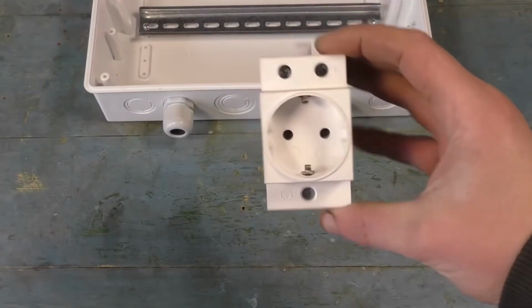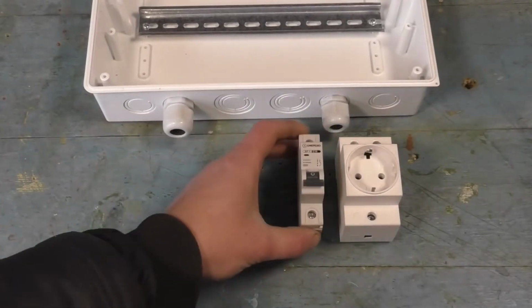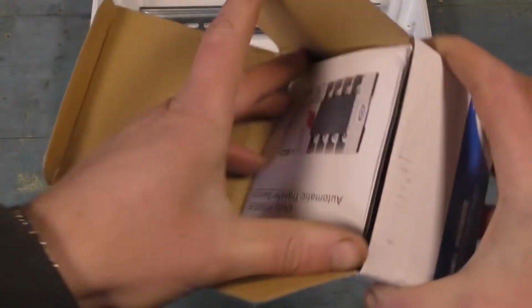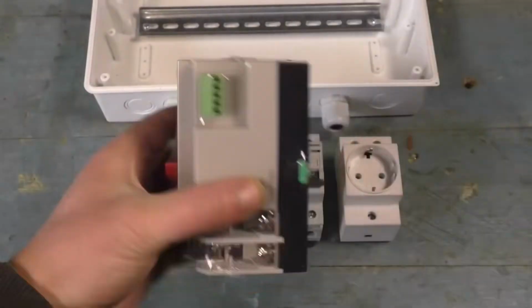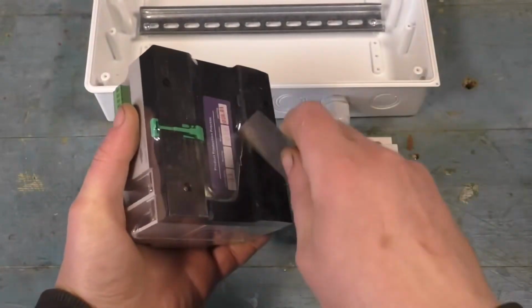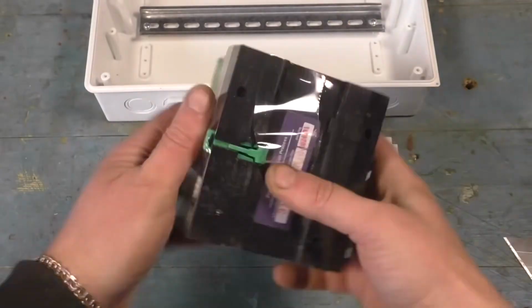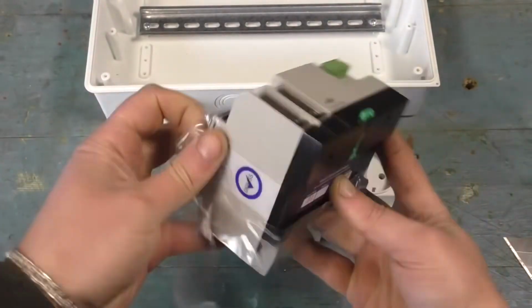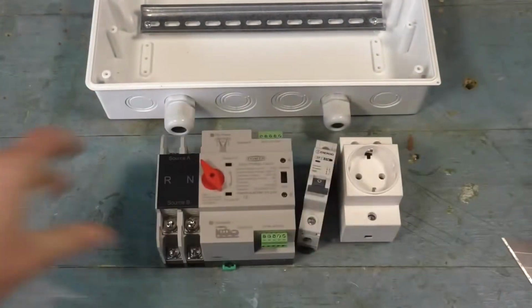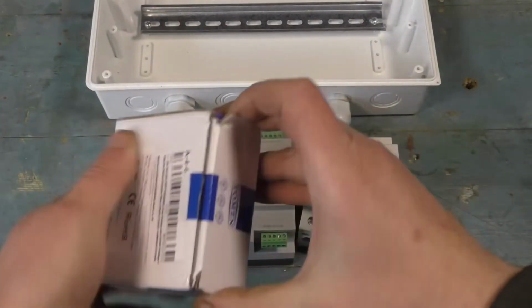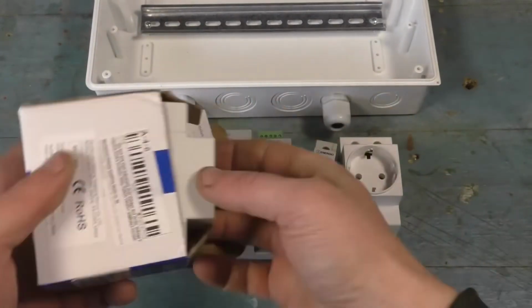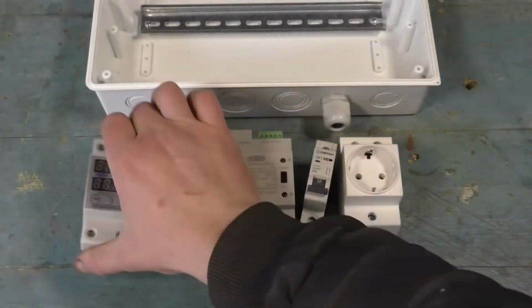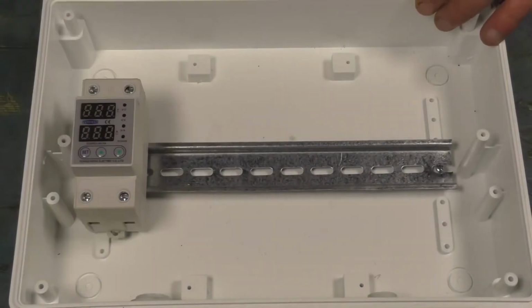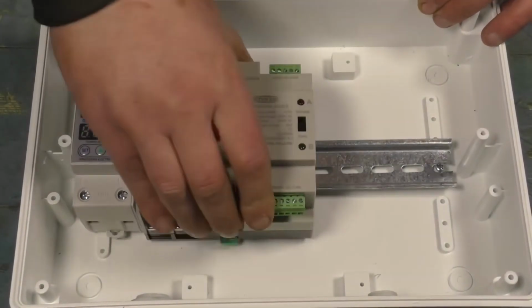Next, we will need a DIN rail socket, a 16 amp circuit breaker and a transfer switch. I'm using a 125 amp model from Tomzien. As you can see, all the components are sealed and absolutely new, so you don't have to worry about the reliability of the panel. And the last module we need is a 40 amp relay for protection against voltage surges. We install all these modules on one rail and move on to connecting them.